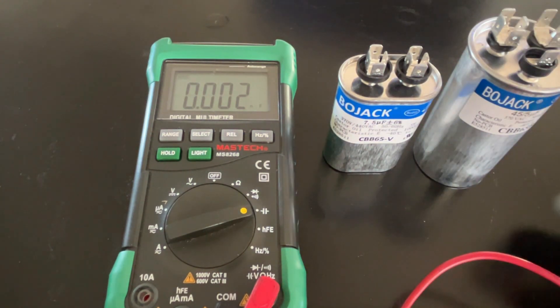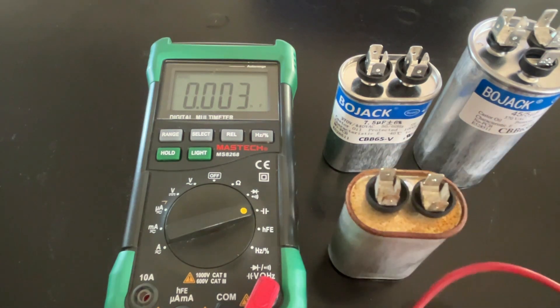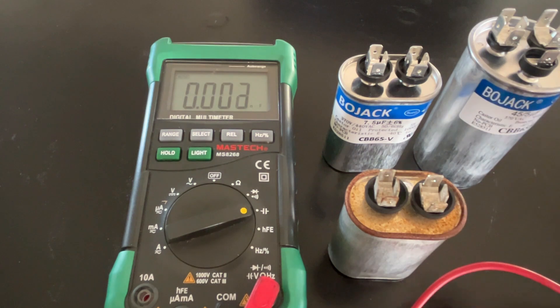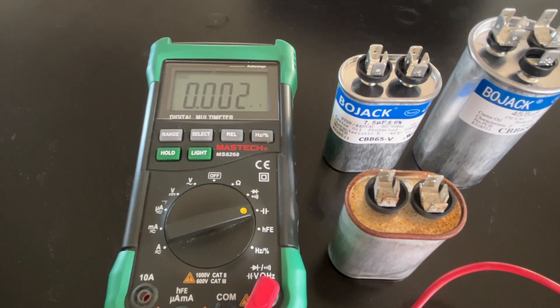So that's how you measure capacitors. Make sure they're discharged before you check them. Make sure when you take it out of the machinery that it's operating, you don't touch the contacts—you'll get a nasty shock. Set your multimeter to the capacitance setting. On these dual run capacitors, you're going to have two different readings—one for the fan and one for the compressor—and you measure both of those against the common. That's all there is to testing capacitors. I hope this video has been helpful to you. I really appreciate you watching. Have a great day.